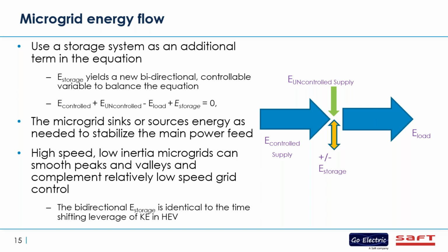The microgrid sinks or sources energy as needed to stabilize the main power feed. So the high-speed, low-inertia microgrid can smooth peaks and valleys, complement relatively low-speed grid control. The high-speed inverter behaves like a damping inertia on the uncontrolled energy feed and effectively becomes synthetic inertia electronically. The bidirectional energy storage is identical to the time-shifting leverage of kinetic energy in hybrid electric vehicles. It's a transference of energy from one form to another.